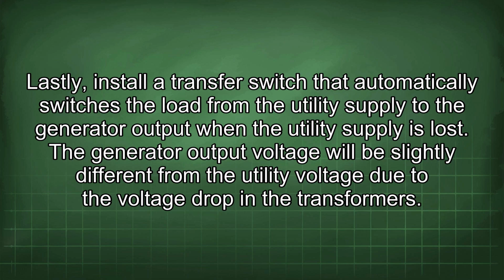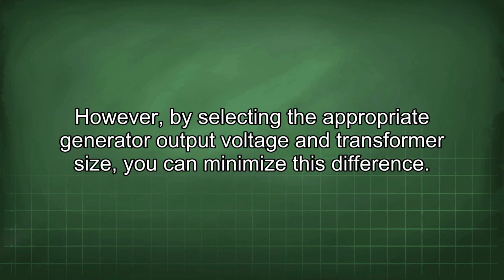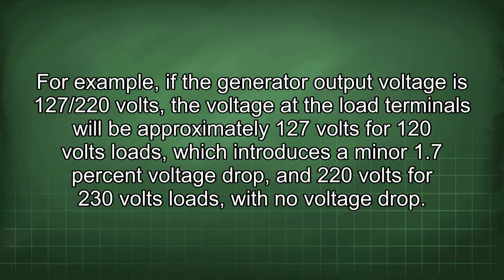The generator output voltage will be slightly different from the utility voltage due to the voltage drop in the transformers. However, by selecting the appropriate generator output voltage and transformer size, you can minimize this difference. For example, if the generator output voltage is 127/220 volts, the voltage at the load terminals will be approximately 127 volts for 120 volts loads, which introduces a minor 1.7% voltage drop, and 220 volts for 230 volts loads with no voltage drop.